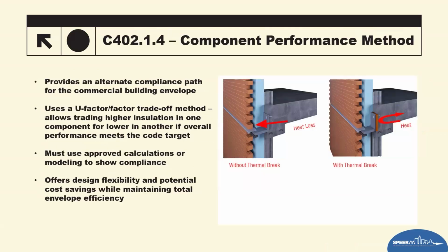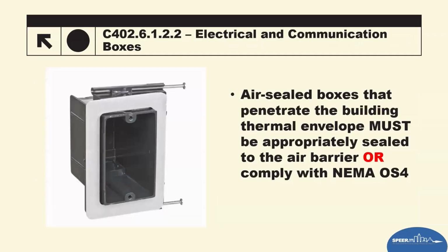Component performance method, there's still one of those similar to the residential side of that. It provides an alternative compliance pathway for building envelopes. It uses the U factor and the F factor trade-off methods, allows for trading higher insulation on one component and lower on another to still meet an overall performance. Must have approved calculations and modeling to show equivalency. So you're using a COMcheck or something that's similar. Offers design flexibility and potential cost savings while maintaining total envelope efficiency as well.